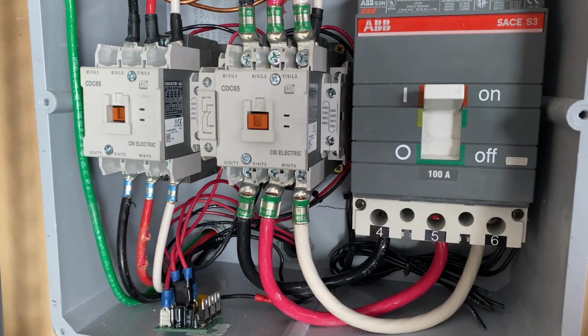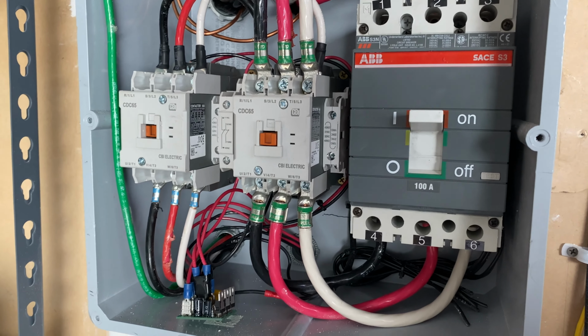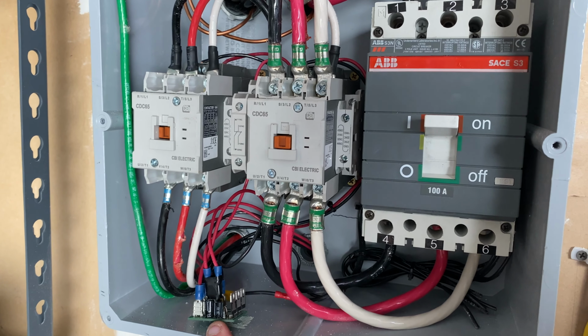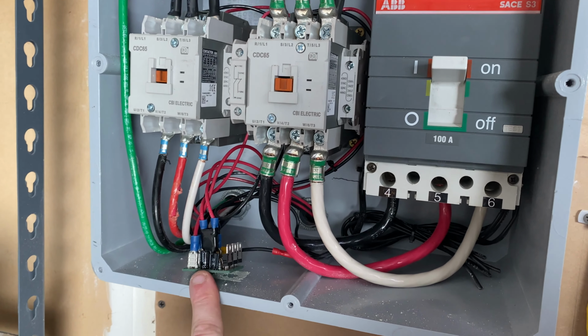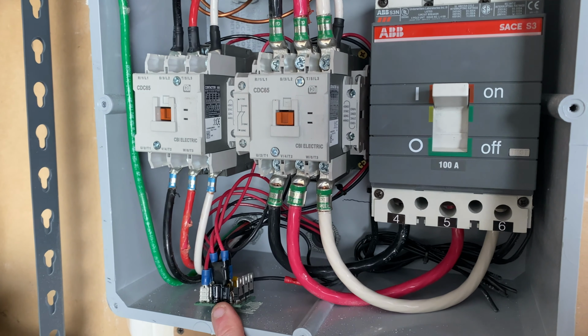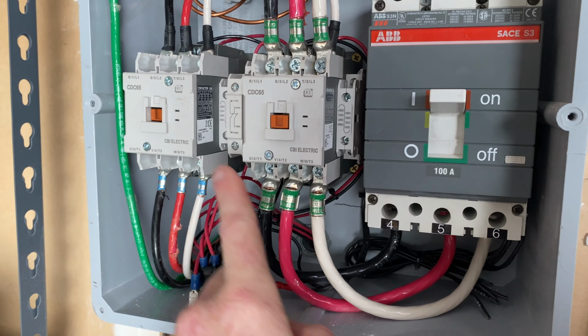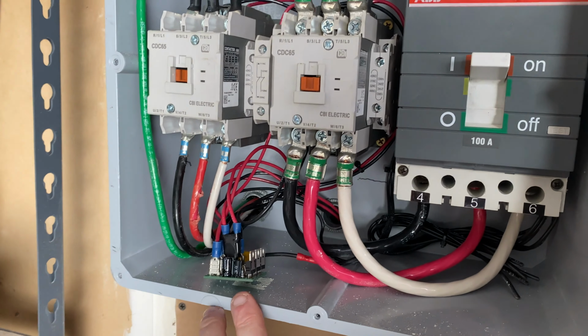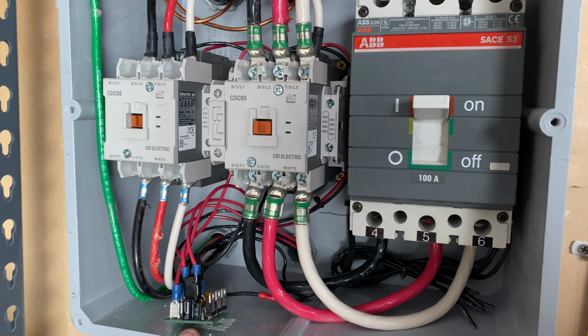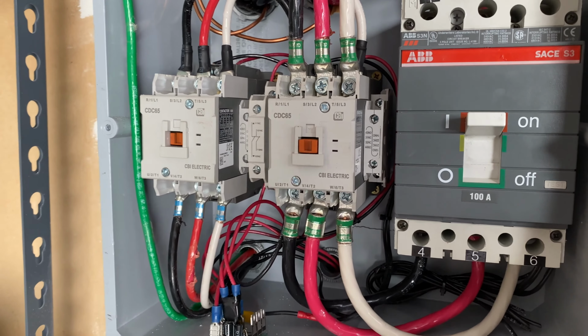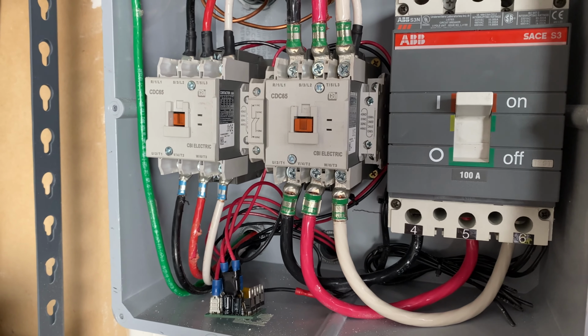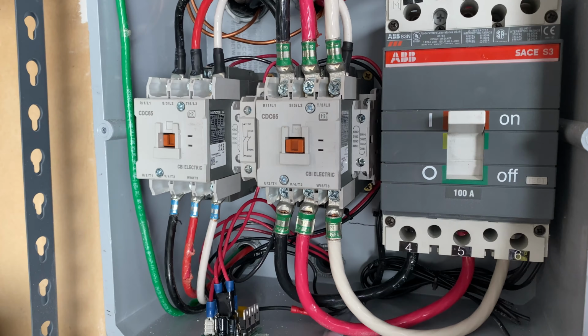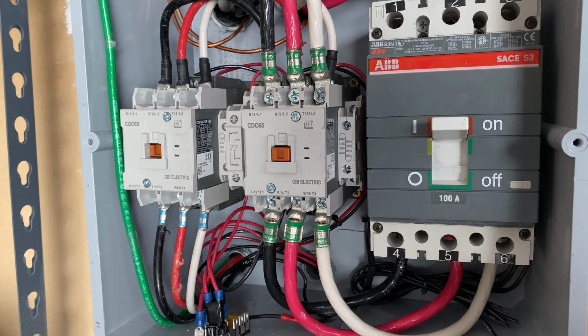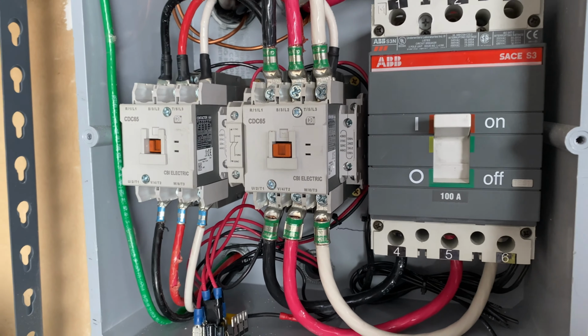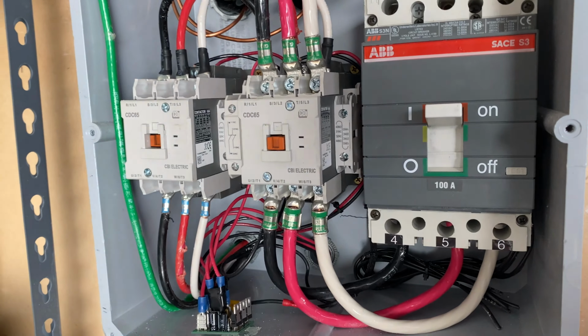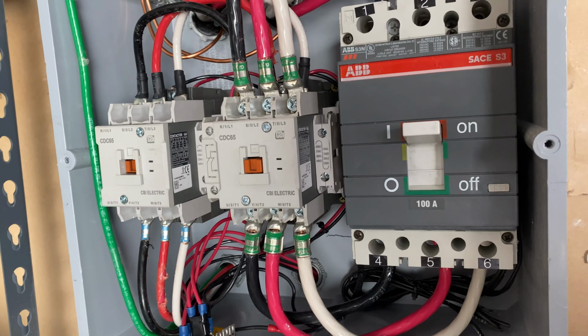Again, I mentioned earlier that there were 24-volt control lines coming from the shed, and that's what is coming into here. So this here is an SPDT relay, solid state of my design. I couldn't find one that was cheap or available at all, so I just designed my own using MOSFETs, and they control the state of these two contactors. It is very fast. It has a 10 millisecond switch time, and it would be faster, but I had to account for the state of the transition of the contactors, because with these specific contactors, you can't load one and have the other one switch. As soon as you load one, it locks the whole system up. And so it's basically a break before make system. So there's a bit of a gap. I haven't actually measured it, but there's a bit of a gap switching between the two sources.